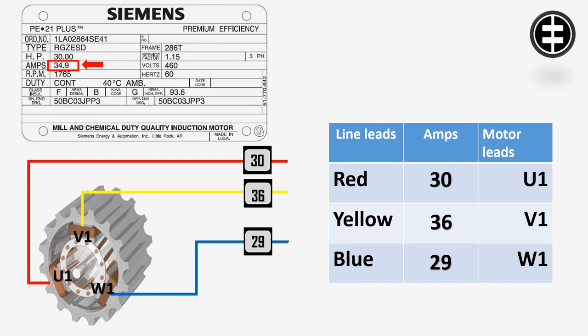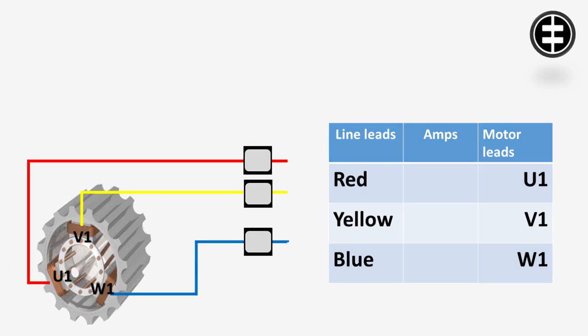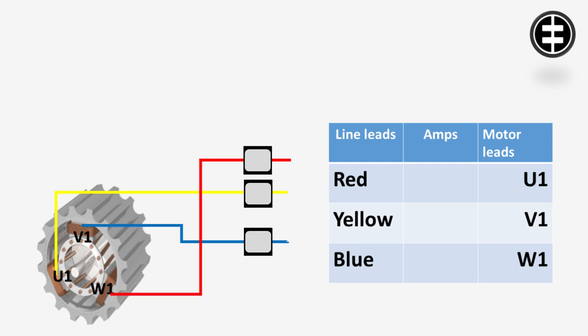Now we will stop the motor and change the connection. Connect the red line lead to W1, yellow line lead to U1, and blue line lead to V1. This is to make the motor rotate in the same direction.